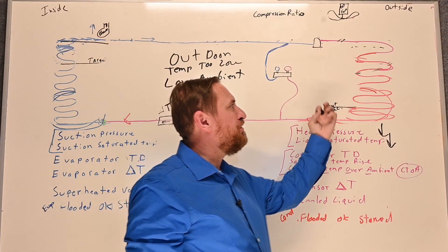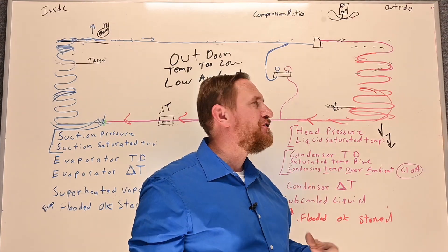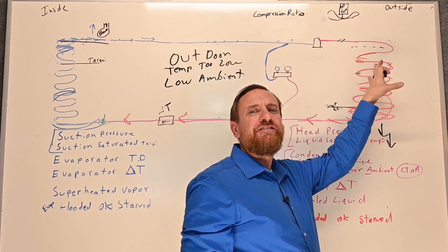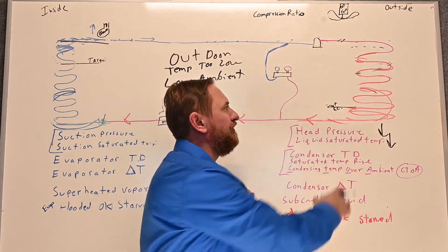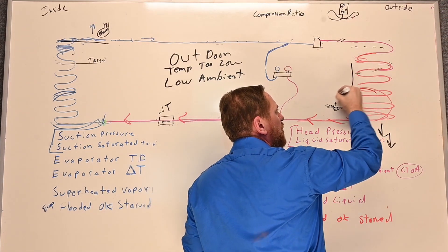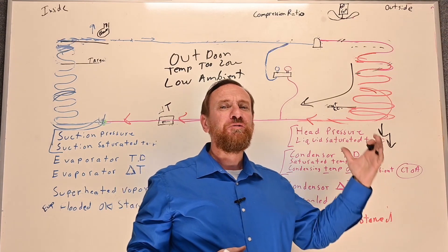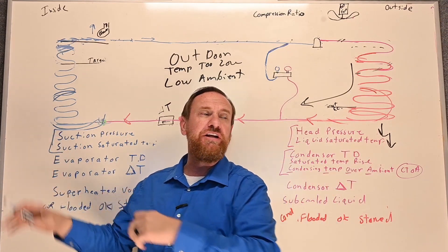So that'll be an issue. Now that we're transferring heat at a very fast rate, a very efficient rate, we end up with less pressure on this outdoor unit. Now, regardless of all these other details, this is the case we're going to look at the pressure alone. I have less pressure pushing on this liquid refrigerant. So ultimately, I don't have enough pressure pushing the right amount of refrigerant to the indoor unit.